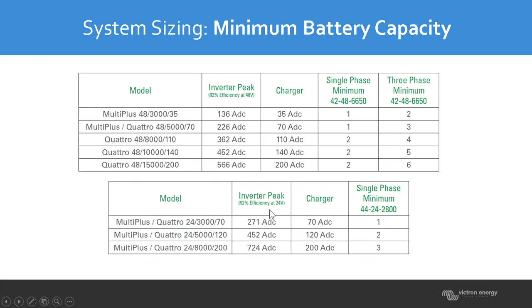So this is something that the good folks at Discover Battery shared with me yesterday. For autonomy, you're just going to size it just like you normally would. You're going to use that 6.65, and that's the useful power in that battery. There's actually 7.4 kilowatt hours, but there's 6.65 of usable. So you size just like you would normally.